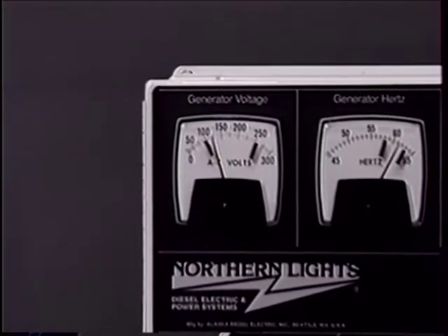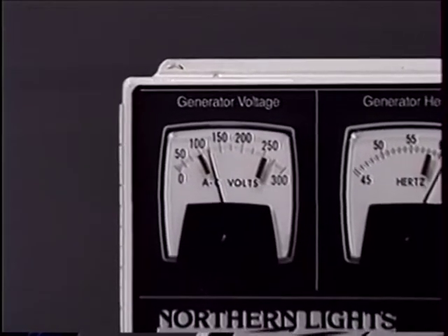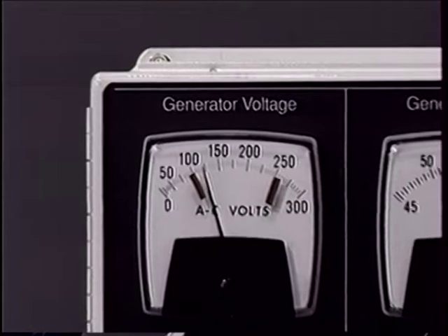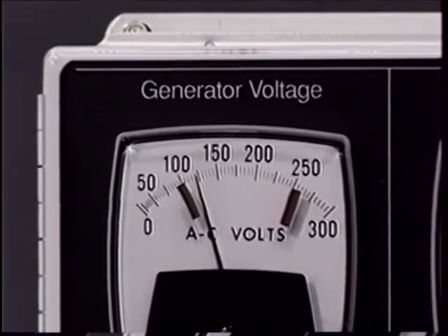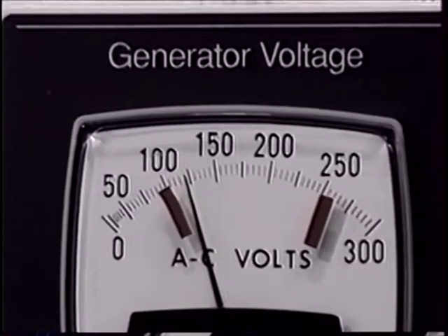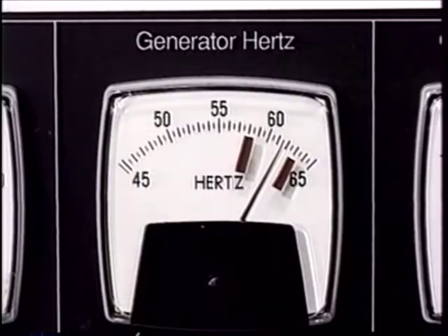Look at your AC voltmeter. For a 120 volt system, the voltage reading should be in the range of 115 to 125 volts AC. Your frequency meter should indicate a 59 to 62 Hz reading for a 60 Hz system. For a 50 Hz system, your readings will be in the range of 49 to 52 Hz. Of course, these readings will depend on the amount of load being applied to the unit.